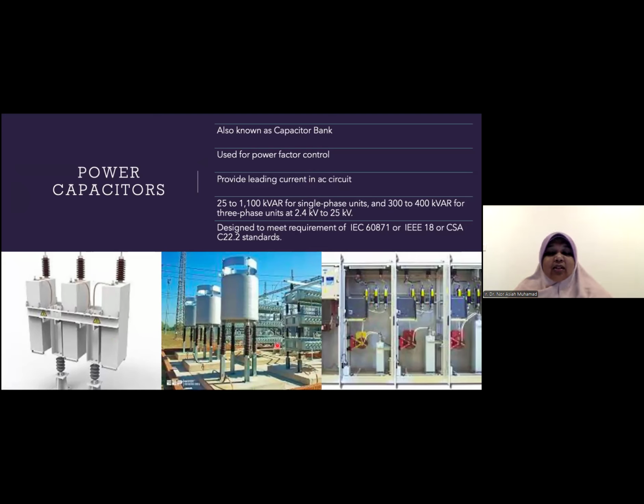So we will have a good P and Q, and it provides leading current in the AC circuit. The rating is between 25 to 1100 kVAR for single phase, and up to 300 to 400 kVAR for 3-phase units. All the designs must meet the requirements of IEC 60871 or IEEE 18, or the CSA C22.2 standard. So this is the indoor, this is the outdoor capacitor bank. This is the indoor or in-cabinet capacitor bank.